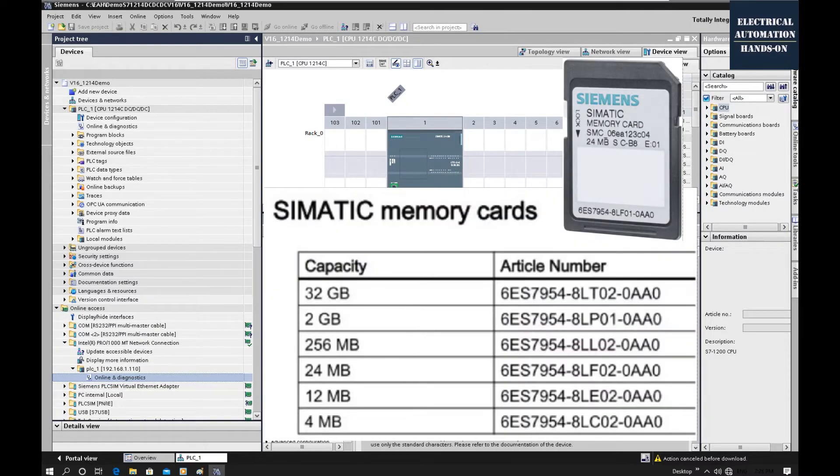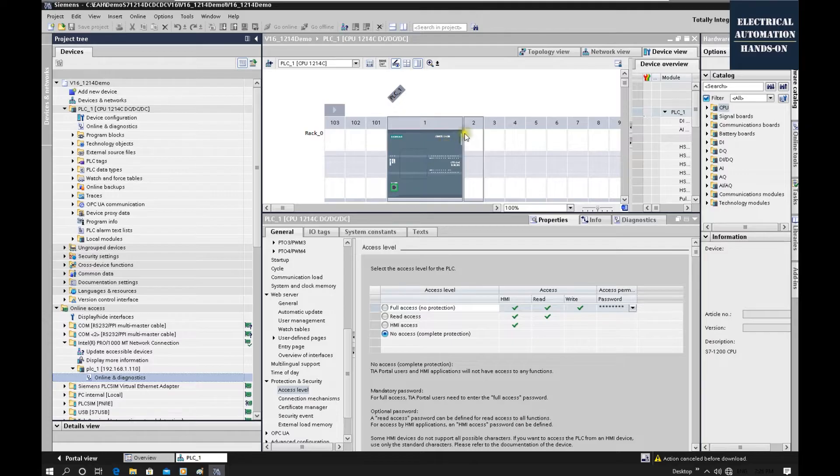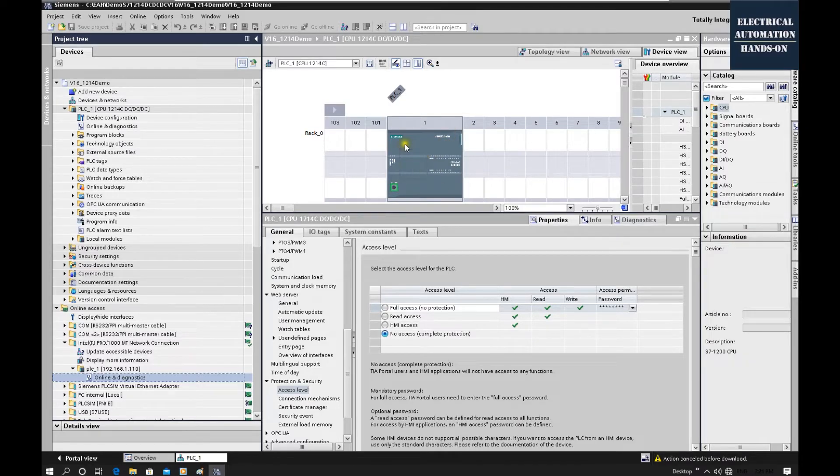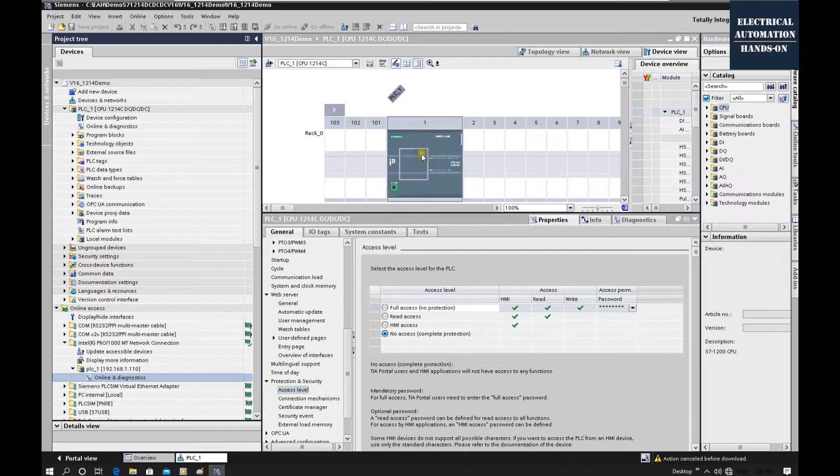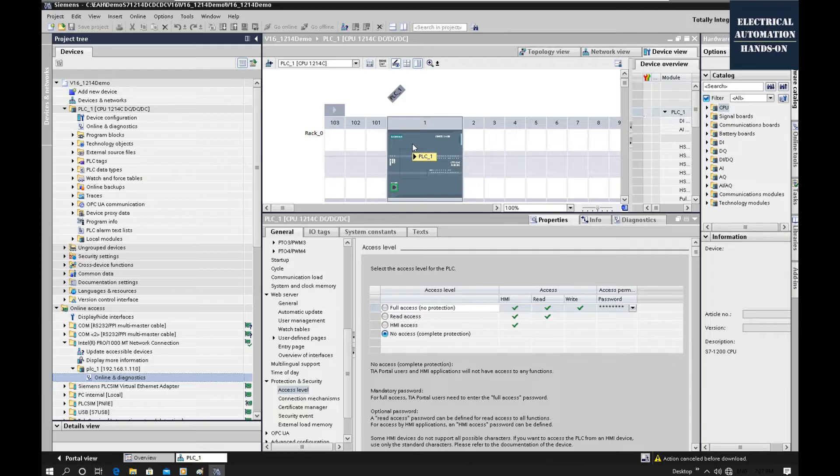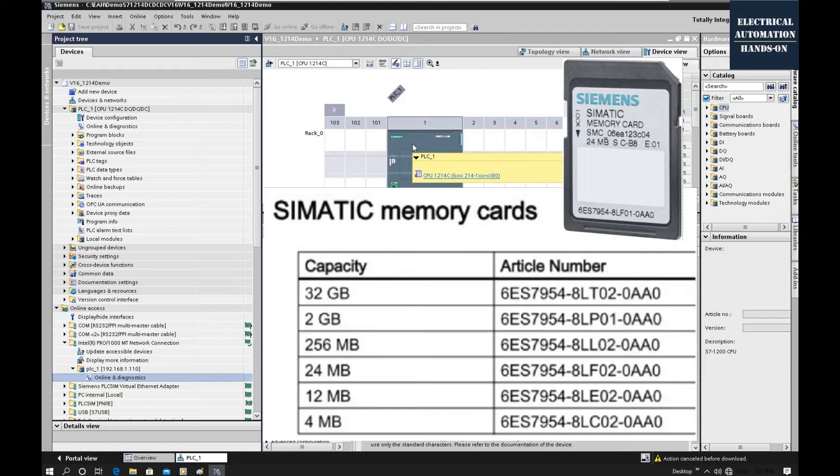So the only way is we will use one empty memory card. The basic idea is once this controller has an empty card, it will transfer the program or some setting inside this CPU, transfer all the setting and program into this empty card. And then this controller will be an empty one. This is the key idea. So you need to use one SD memory card reader and plug in this Siemens Simatic memory card into this reader.